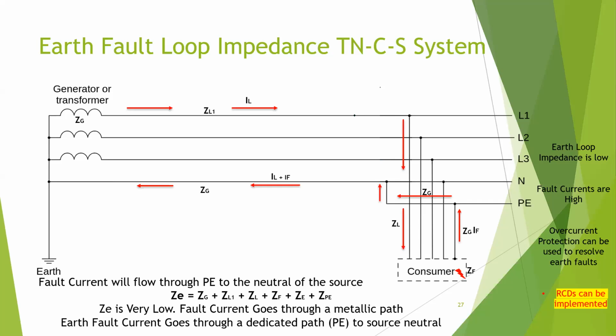So the current through here and here will be equal because the fault current is also combining with the line current from this point onwards. But if you use the RCD at these 2 points, we can have the differential protection. So that is the advantage of the TNC system. So I think you understood that. Did you understand the TNC system? It's the TNCS system. So this is actually similar to TNS, but we are acquiring the same protection level at a lower cost.